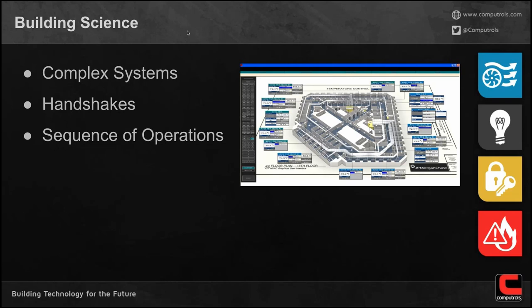Getting back to the HVAC handshake I was speaking of, as a result of that smoke detector being triggered, that may trigger a smoke evacuation sequence on the HVAC system. When that happens, the HVAC system may shift gears from a cooling standpoint, an occupant comfort standpoint, to a means of evacuating smoke from the building so it doesn't build up and affect the building occupants. So, a lot of different sequences, a lot of different scenarios.